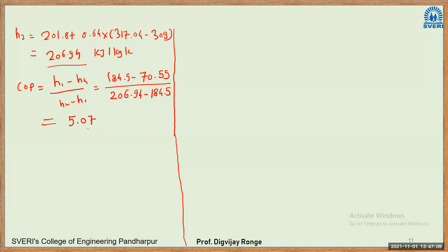So now calculate the COP. Let us see how many of you have calculated. 5.07, 5.09. So there are two values. I'll take 5.07 randomly. This is the theoretical COP. Now what they have told here is that the actual is 0.65 times theoretical. So COP actual will be equal to 0.65 into COP theoretical, which is 0.65 into 5.07. So calculate this one. This will be your actual COP.